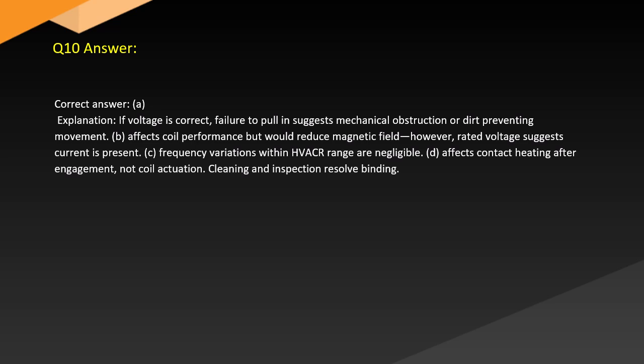Answer. Correct answer: A. Explanation. If voltage is correct, failure to pull in suggests mechanical obstruction or dirt preventing movement. B. Affects coil performance but would reduce the magnetic field. However, rated voltage suggests current is present. C. Frequency variations within HVACR range are negligible. D. Affects contact heating after engagement, not coil actuation. Cleaning and inspection resolve binding.